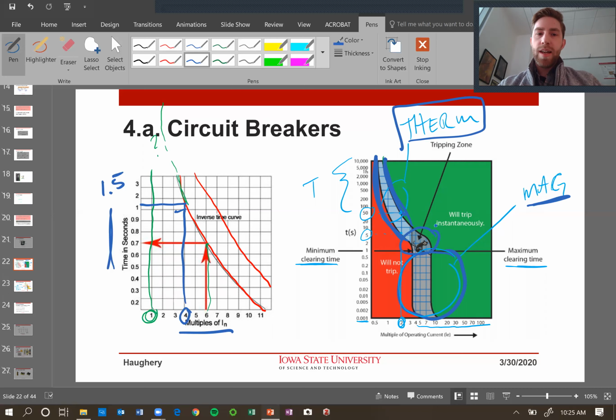And of course we have a top and bottom, or low tolerance, high tolerance: the quickest it will trip or the longest it will trip. And so as you go up in a vertical direction, you're going to hit the bottom part of the curve, right? My hand's right here. First, that's the quickest it will trip, and then the high point is the longest it will trip. So there's a dead band, there's a tolerance like we have in most things in life. We have the fastest it's going to trip versus the slowest it's going to trip, and it's always a range.